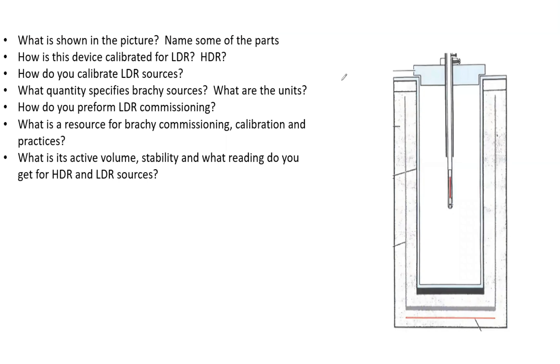This is a well-type ionization chamber. One important note is that we have argon within this chamber at 12 ATM. That argon fills the interior of the chamber.